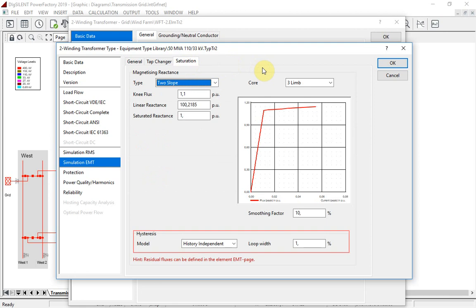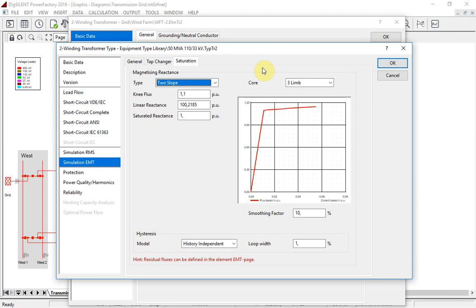The history-independent hysteresis model is supported for all models with saturation. The hysteresis loop is based on the loop width defined by the user and the saturation curve. For this transformer type, a loop width of 1% is defined. The following simulation shows the magnetic flux-current relationship for this transformer, including hysteresis.